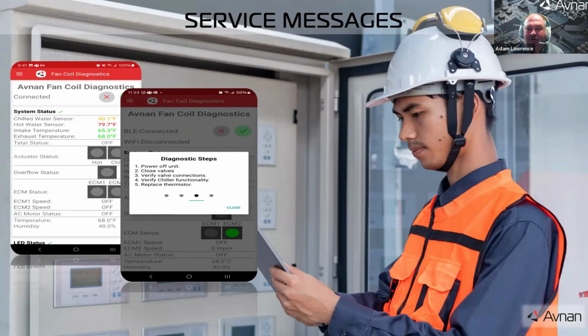In some cases, the controller might even take preemptive actions when a fault is imminent and pop up a warning like "airflow low, check ducts or blower," before it triggers a high-pressure cutout. This kind of proactive diagnostic is aligned with the broader industry trend of predictive maintenance, of using analytics and rich diagnostics to reduce unplanned downtime by enabling proactive service.